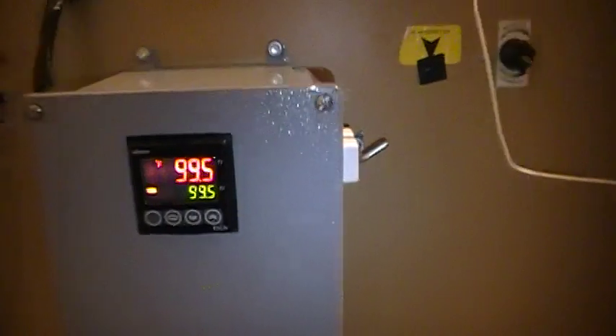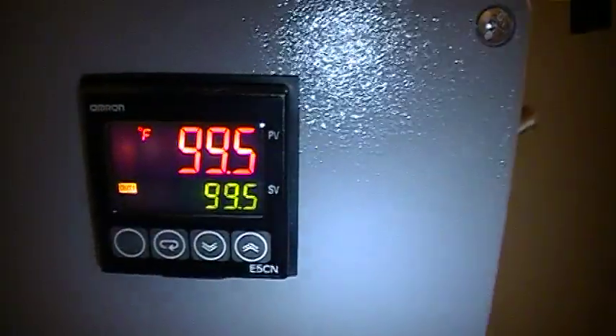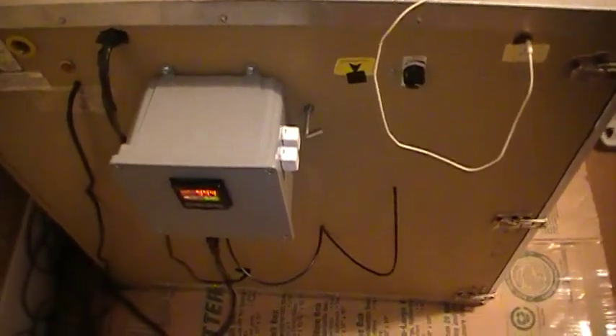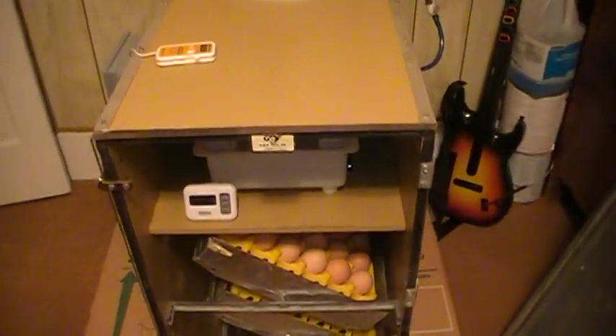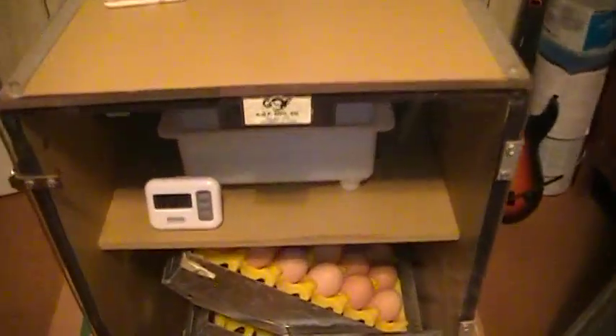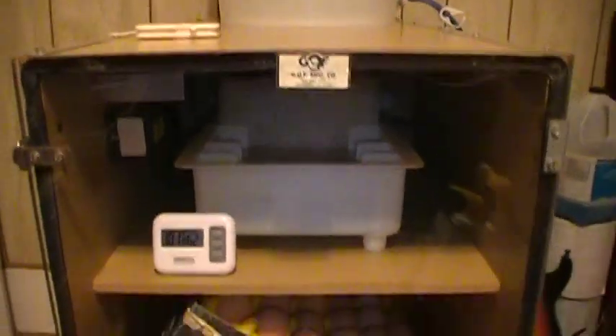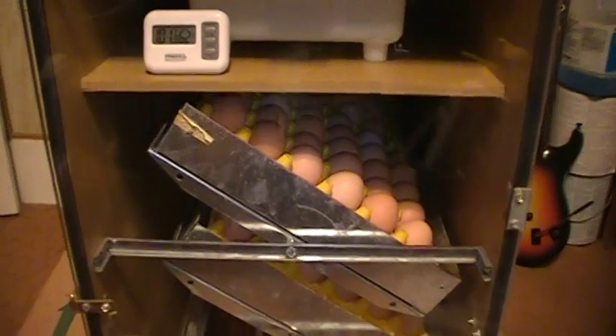But just again for a quick review, this is a Fuzzy Logic electronic temperature control from Omron. The probe is made by Omega. It is an RTD type probe. These two units together run you about $300, and if you already have the thermostat, or the incubator rather, it's just a simple matter of cutting a couple of wires and tying everything back in, and you wind up with a real good setup.